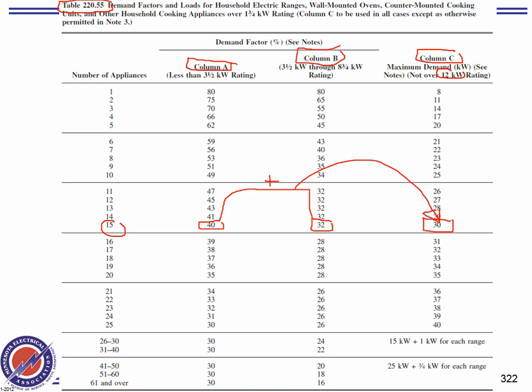I will give you the demand for all these. So this is not number 2. Note number four, guys. This is a branch circuit. You use it to size a branch circuit. Note number four says yes, you can use it for all ranges or for a branch circuit for one counter cooking unit.